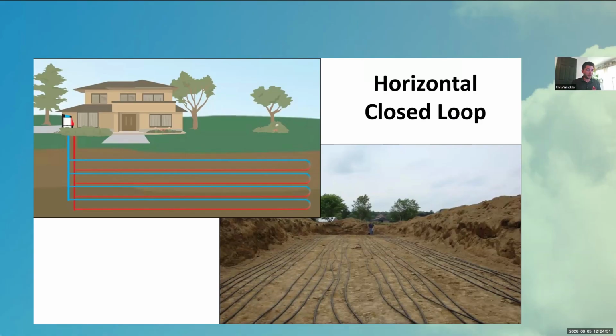Yeah. So, of course, my most favorite answer is it depends. But I'd say on residential systems, we usually target a minimum entering water temperature of around 32 degrees, so around freezing, which is why a lot of these systems have antifreeze in them. And that's because if you look at the temperature difference and the efficiency difference of installing for a higher temperature, say 40, the efficiency increase doesn't make sense from the financial increase of how much more borehole that you'll need. So designing to a higher water temperature on a residential system doesn't make sense. So we typically go to around 32 degrees, maybe 30 for a residential system. On commercial systems, they're actually much higher.